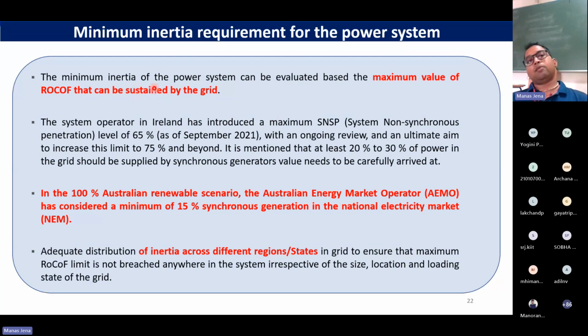The minimum inertia of the power system, how can we evaluate it? Think of this: instead of asking how much maximum penetration of IBRs I can allow, just tweak the problem. What is the minimum inertia requirement? So let us say the minimum inertia requirement we decide based on the maximum RoCoF that my grid can survive.